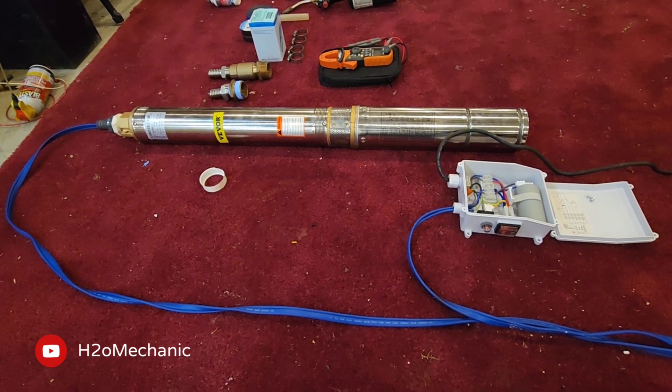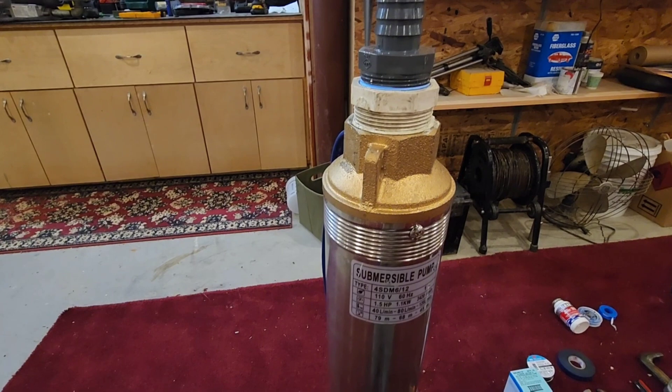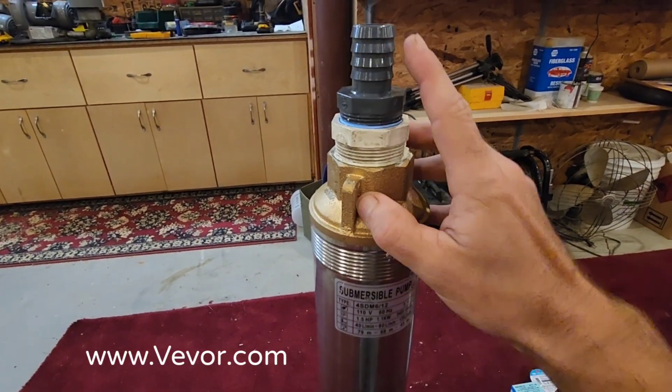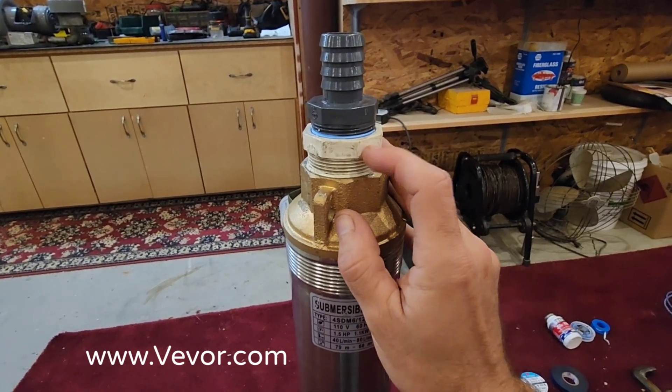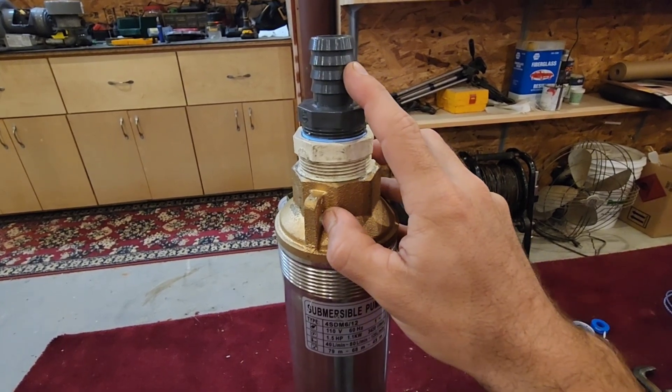This VEVOR well pump is a three-wire 115-volt pump. Since the pump has an inch and a half discharge, if you are trying to adapt it to one inch pipe, you're going to need an inch and a half to inch and a quarter reducer, and then you're going to need your inch and a quarter to one inch barb fitting.